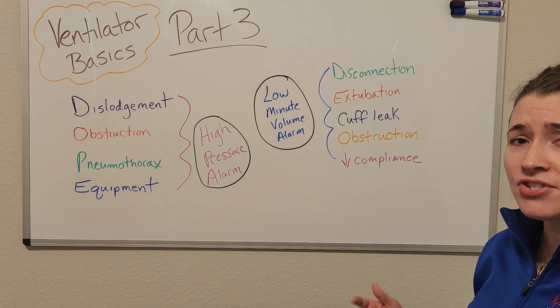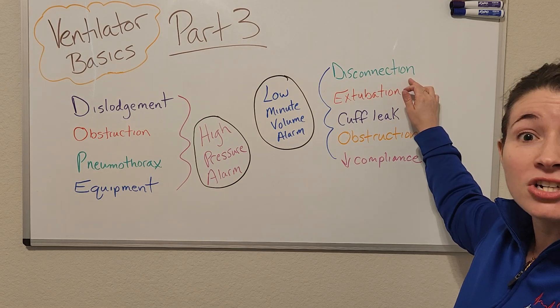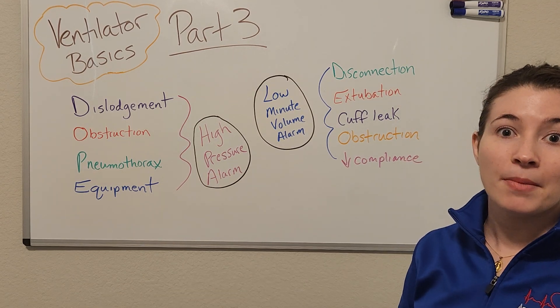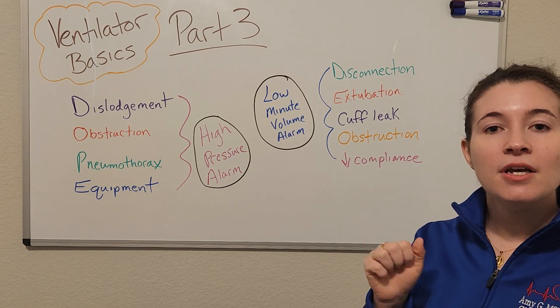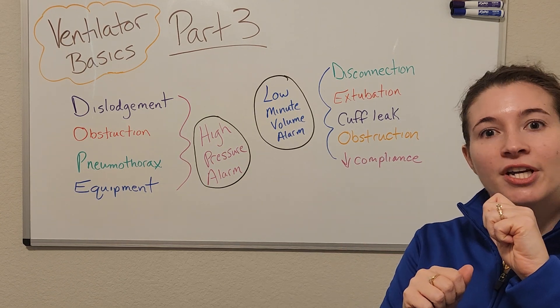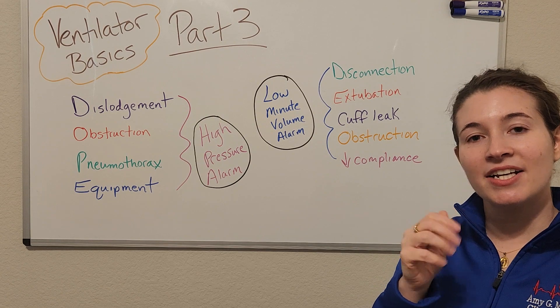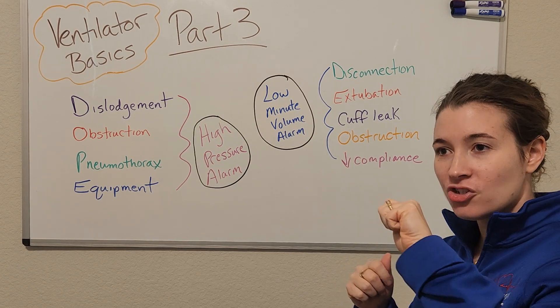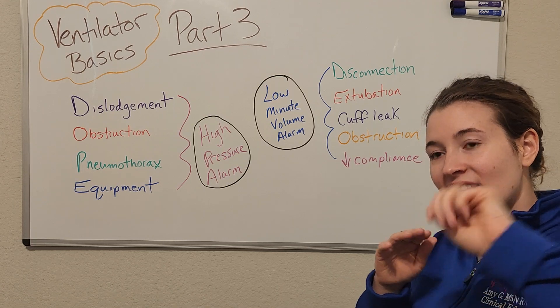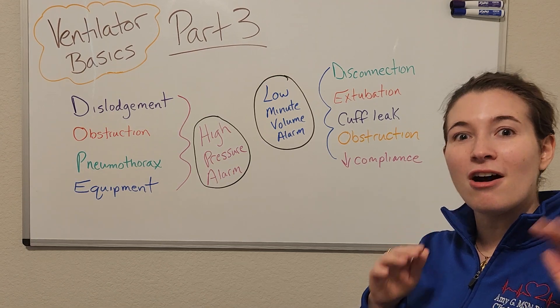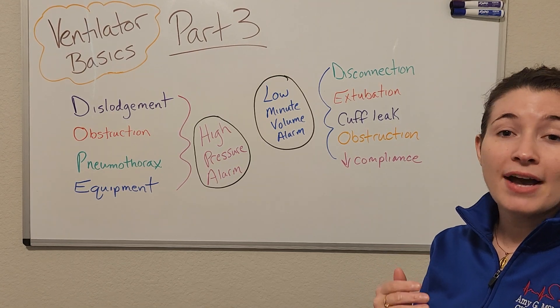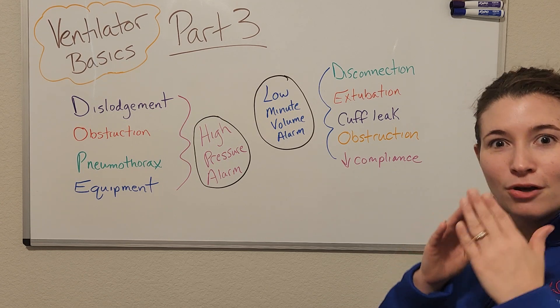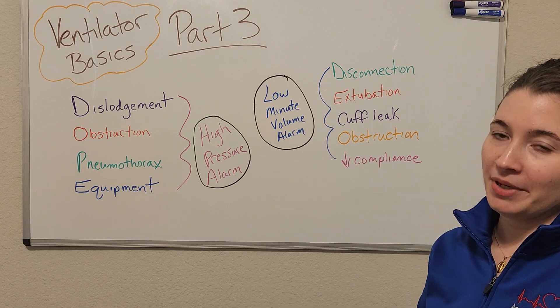Our most common cause of a low minute volume alarm is disconnection — sometimes called popping off the vent — where the circuit tubing becomes disconnected from the actual breathing tube. We see this a lot when turning patients, where the tubing stretches and pops off. To remedy that, we would reattach the circuit tubing.